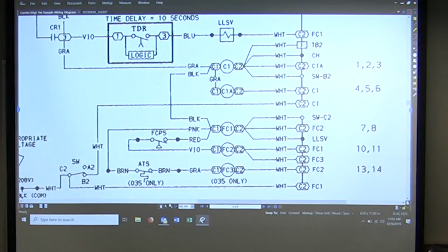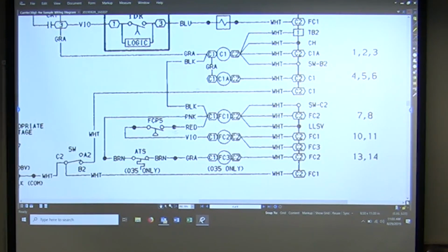So we come down here, and now here's my compressors, right? Those are energized. And then I have some stuff here. What does this stuff do? Fan contactors. So 3 different fans. The first fan comes on immediately, automatically. The second one comes on and off by a pressure switch. The third one comes on for this model by some sort of temperature switch, ambient temperature. There you go. So if you've got this model 035, that one's in there. If not, we're just going off of these 2 here, right?